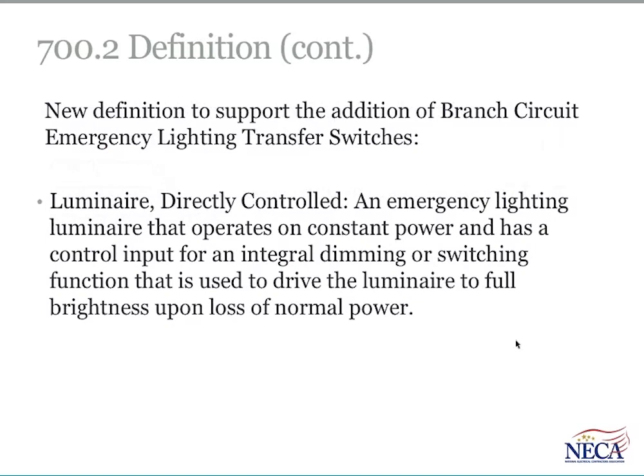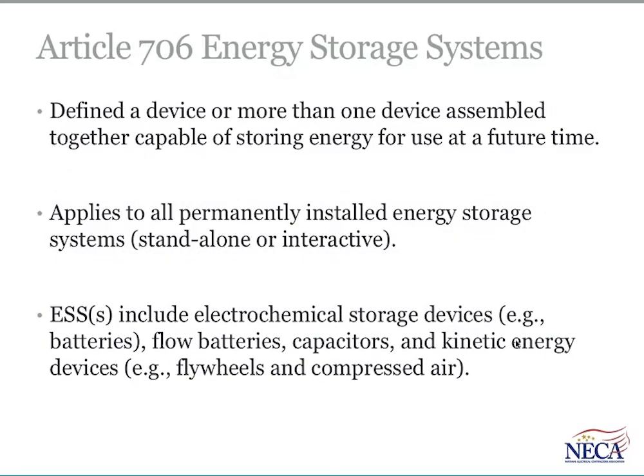And that new definition of branch circuit emergency lighting transfer switch is accompanied by luminaire directly controlled, which is an emergency lighting luminaire that operates on constant power. Often they're used for night lights, but they're also capable, with control leads, of integral dimming or switching functions. So in theater type applications and so forth, you can still control the emergency lighting, but when the power is lost and it has to switch to the emergency mode, it's driven to full brightness so that we don't leave the area in total darkness. So those are a couple of new definitions of terms used within Article 700 dealing with emergency systems.